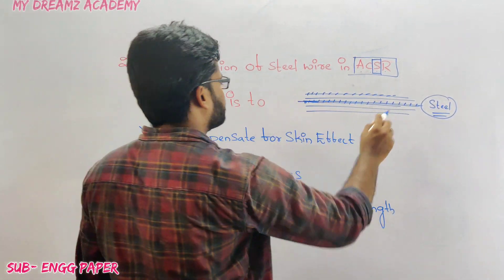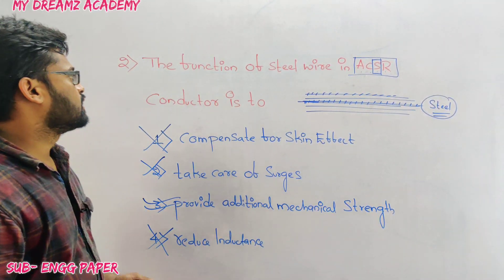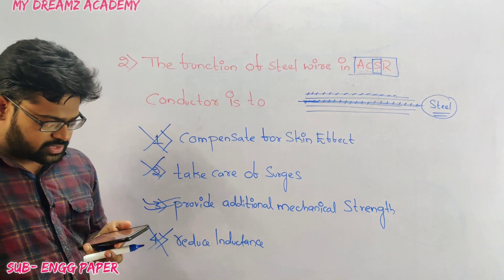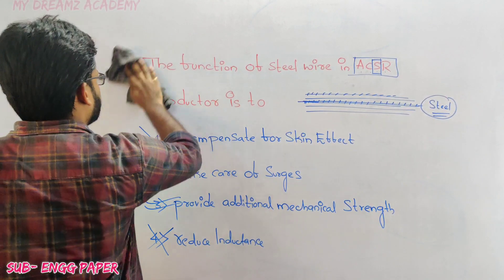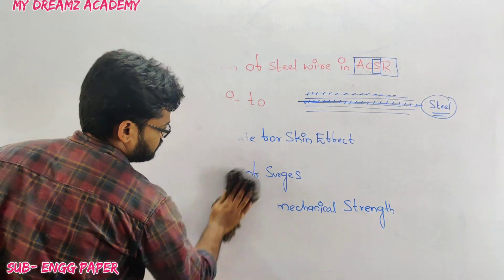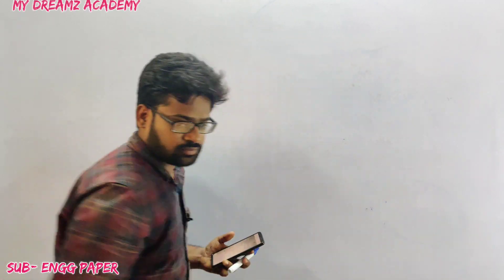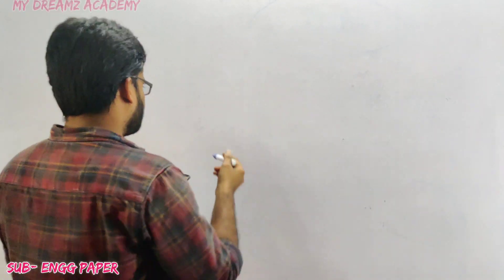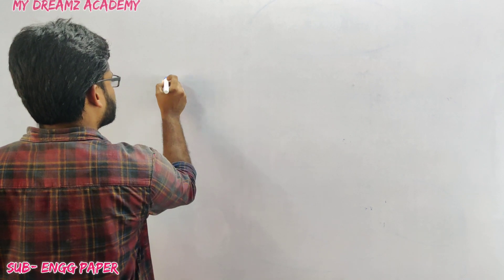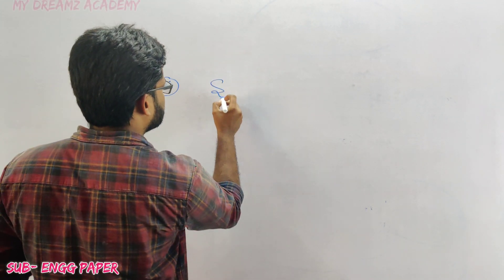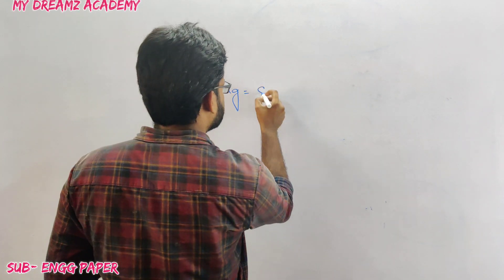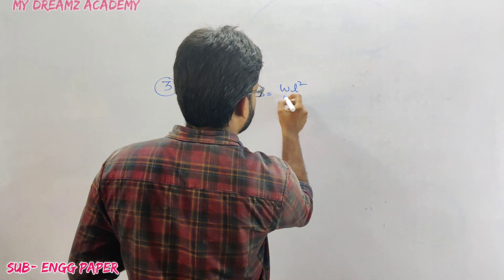Steel does not compensate for the skin effect, it does not take care of surges, and it does not reduce the inductance of the conductor. That is the function of steel wire in ACSR conductor. Question number three is from sag calculations in power systems. The sag formula is S = wL²/8T, where w is the weight of the conductor and T is the tension.